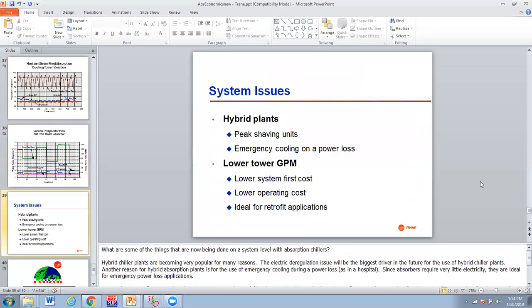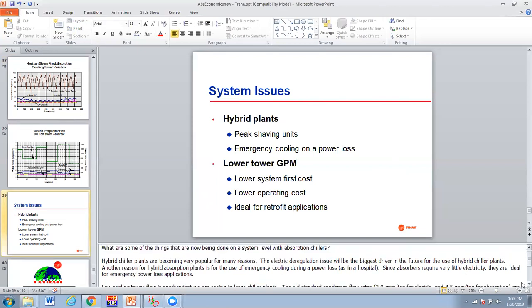Okay, let's see, some system issues: hybrid plants used for peak shaving, and emergency cooling on power loss. We don't need hardly any electrical, a little bit to run pumps. So if you're on an emergency generator with limited capacity, the absorber is much easier to keep online. Such as a hospital would be an example of that, so very little.